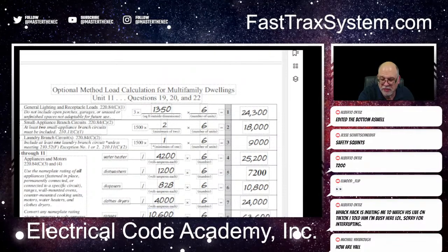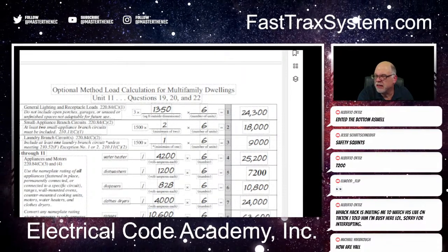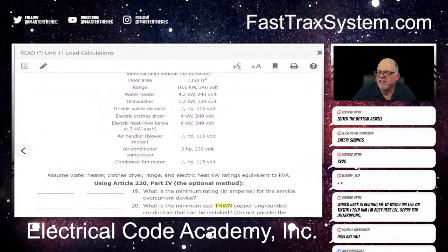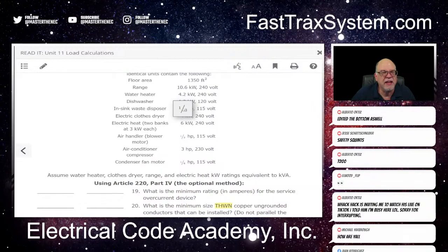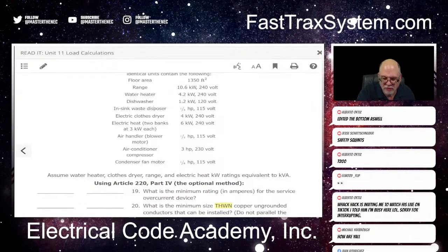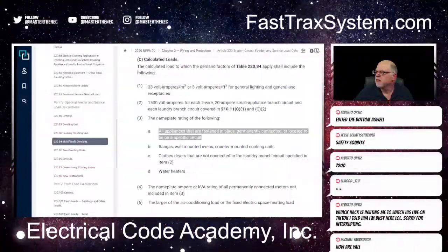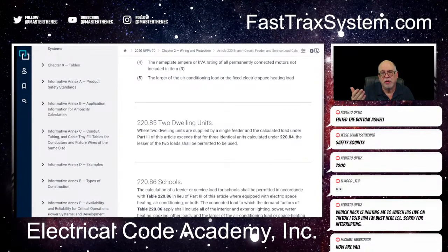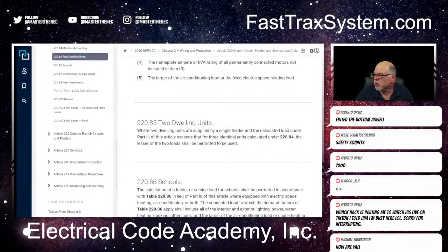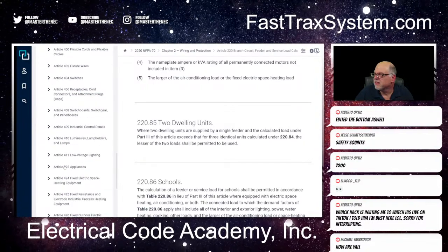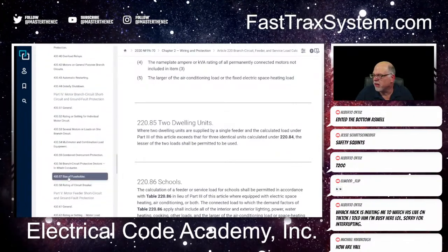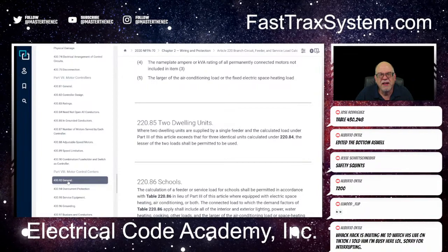Okay. So anyway, let's go to the NEC real quick. No, let's go to the lesson real quick. So we'll go to the lesson. Okay. And so in this lesson, it is a 3rd horsepower, right? I'll click on this so you can see it. 3rd horsepower. So where do we go? We got to go to the NEC. So let's go to the NEC. And in the NEC, where do I go to get the FLC of a motor? Y'all know where to go. All right. So we're going to go to 430. And let's see, 430. And we're going to go down to 430.248, right? Right? There you go.